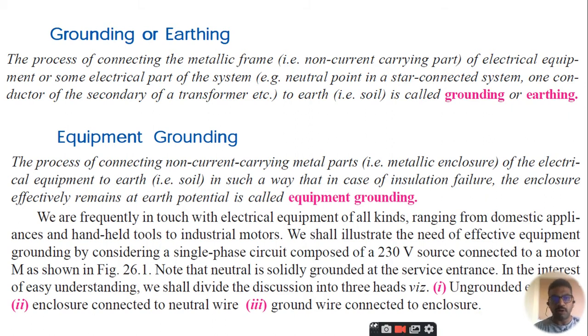This is also known as equipment grounding, where the process of connecting the non-current carrying metallic part, that is the enclosure of the electrical equipment, to the earth in such a way that in case of insulation failure, the enclosure effectively remains at earth potential, is called equipment grounding. We are frequently in touch with electrical equipment of all kinds, ranging from domestic appliances to handheld tools to industrial motors. We shall illustrate the need of effective equipment grounding by considering a single phase circuit composed of a 230 volt source connected to the motor, and note that the neutral is solidly grounded at the service entrance.